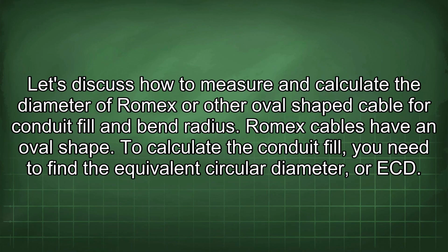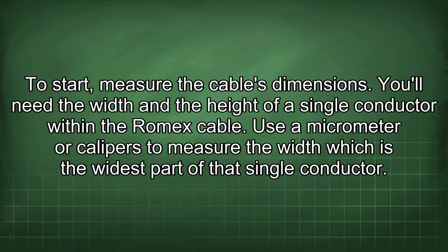Let's discuss how to measure and calculate the diameter of Romex or other oval-shaped cable for conduit fill and bend radius. Romex cables have an oval shape. To calculate the conduit fill, you need to find the equivalent circular diameter, or ECD. To start, measure the cable's dimensions.